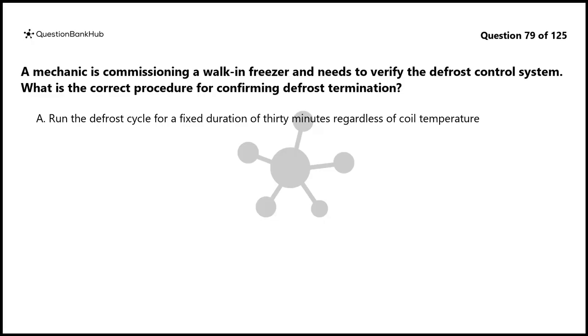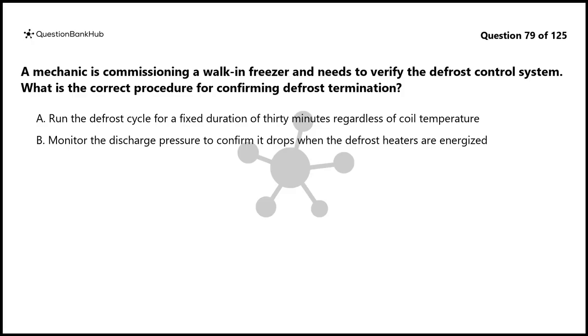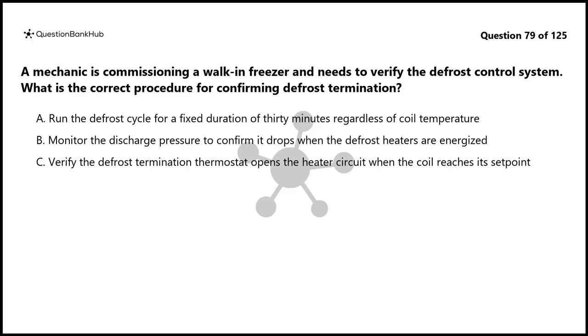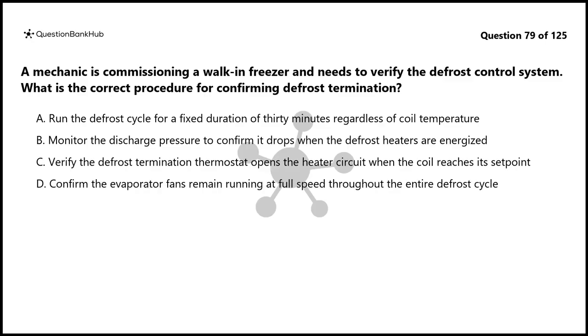A. Run the defrost cycle for a fixed duration of 30 minutes regardless of coil temperature. B. Monitor the discharge pressure to confirm it drops when the defrost heaters are energized. C. Verify the defrost termination thermostat opens the heater circuit when the coil reaches its set point. D. Confirm the evaporator fans remain running at full speed throughout the entire defrost cycle.